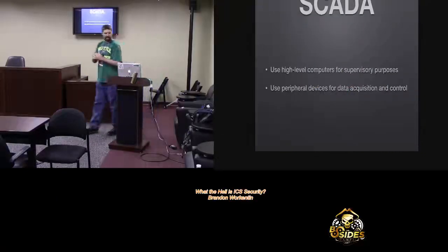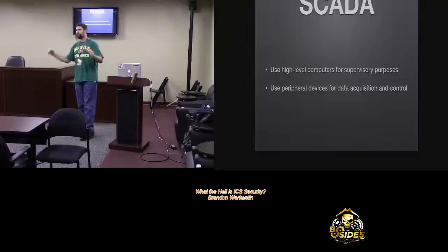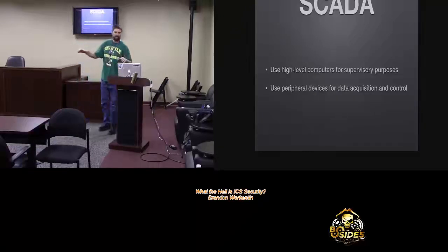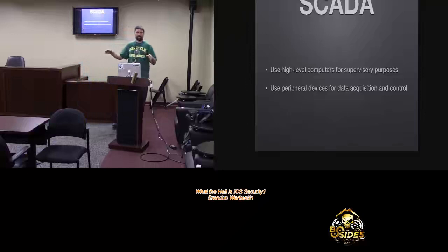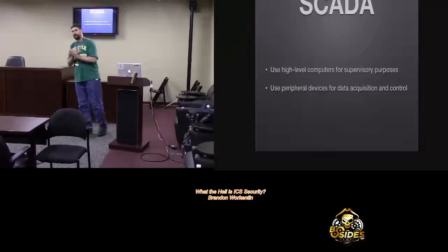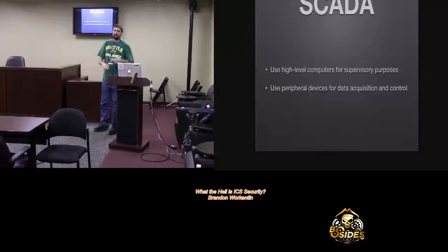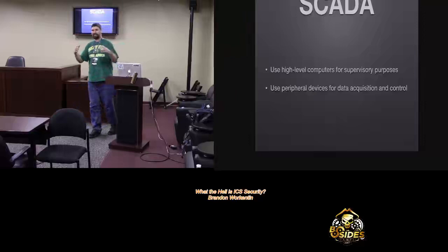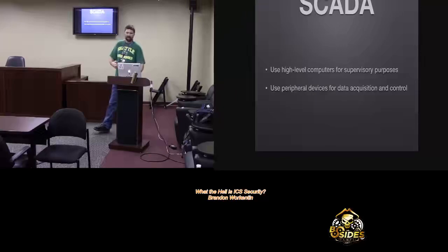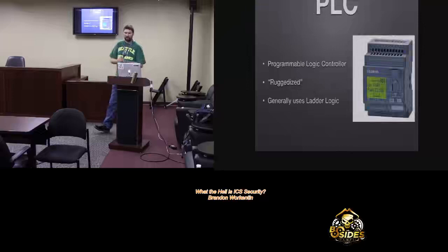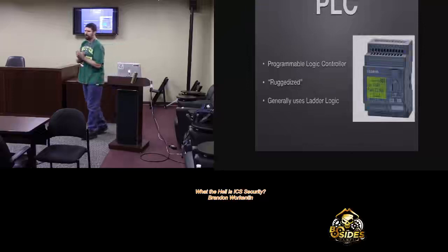The main thing about SCADA is it uses high-level computers for the supervisory process, and peripheral devices for the data acquisition and control. Those peripheral devices are often distributed, not on that computer. If distributed over miles, we call it a distributed control system, or DCS, another common acronym. The most common term for those peripheral devices is probably PLC, or programmable logic controller.